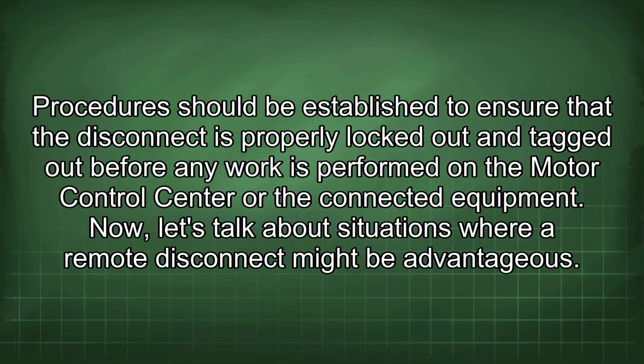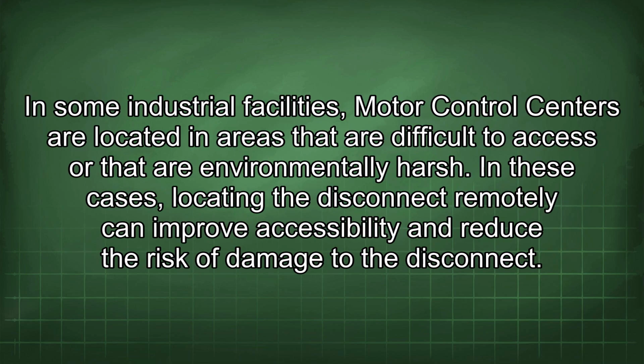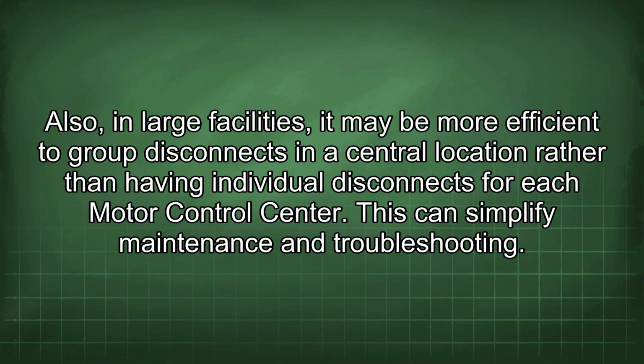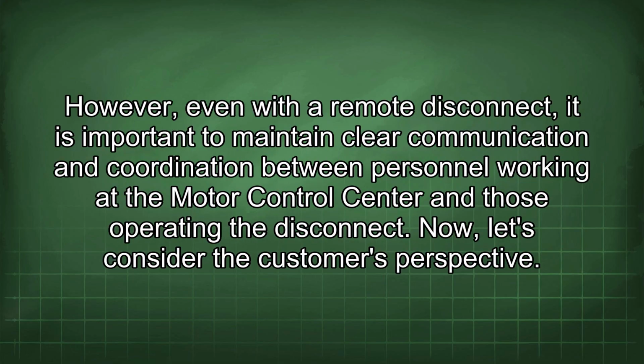Now let's talk about situations where a remote disconnect might be advantageous. In some industrial facilities, motor control centers are located in areas that are difficult to access or that are environmentally harsh. In these cases, locating the disconnect remotely can improve accessibility and reduce the risk of damage to the disconnect. Also, in large facilities, it may be more efficient to group disconnects in a central location rather than having individual disconnects for each motor control center. This can simplify maintenance and troubleshooting. However, even with a remote disconnect, it is important to maintain clear communication and coordination between personnel working at the motor control center and those operating the disconnect.